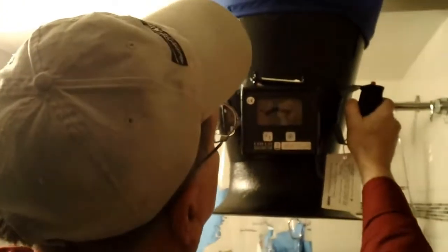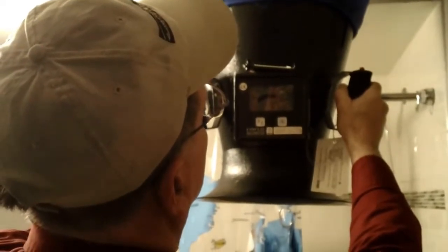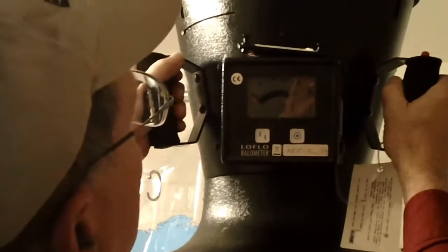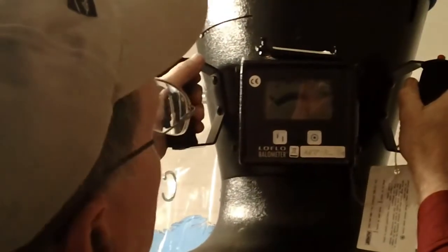This is the fourth bathroom in this particular house, and it has a new Energy Star fan installed. Let's see how it's ventilating. And this one is also doing quite good. Again, it's measuring about 74 cubic feet of air per minute, 75, and that's very good for a bathroom like this that gets a lot of high use. Again, get the moisture out of the bathroom.